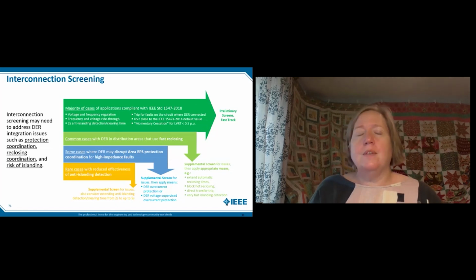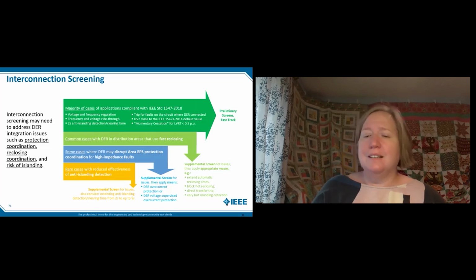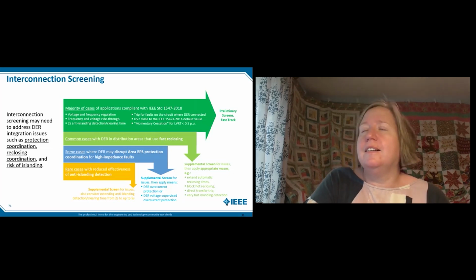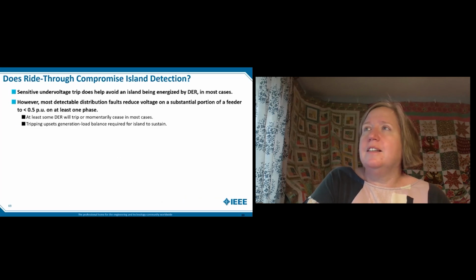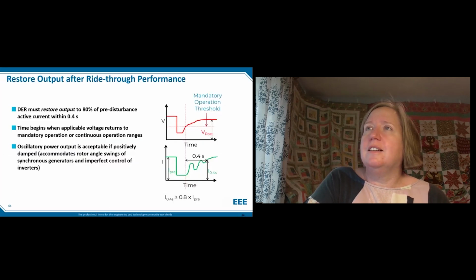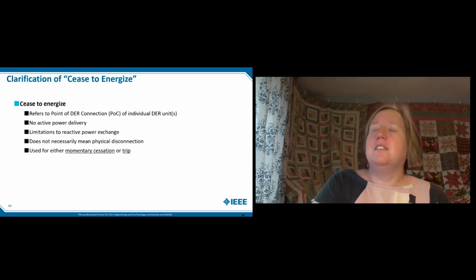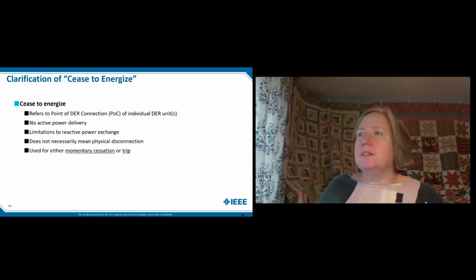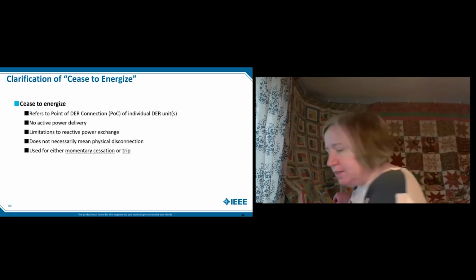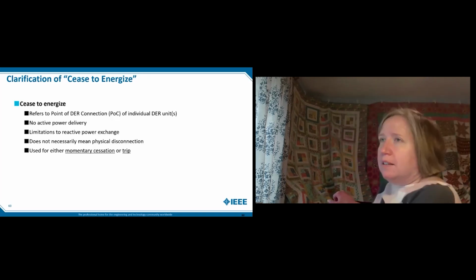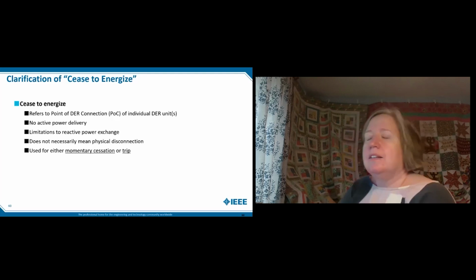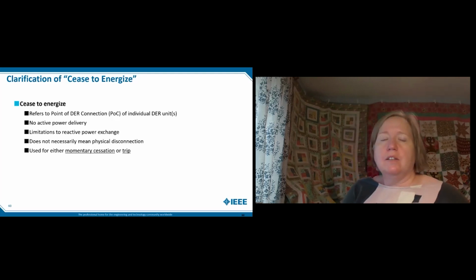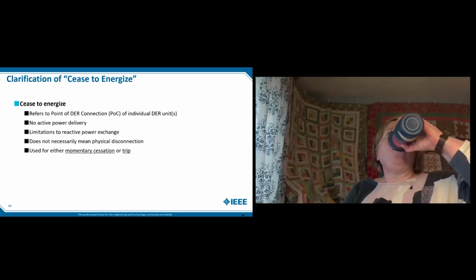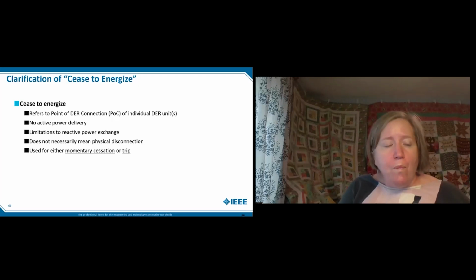We have a lot of time. I would like to back up to one concept and get your thoughts. The 2018 revision added the whole concept and the metrics around cease to energize. A key aspect of cease to energize is the asset is still parallel to the grid, but not injecting real power for a defined duration. It helps determine whether the grid is going to go black or continue operating. I added a link to the Blue Cut Fire event report, where the bulk power operators were surprised to see the DER remained off a minimum of 5 minutes.